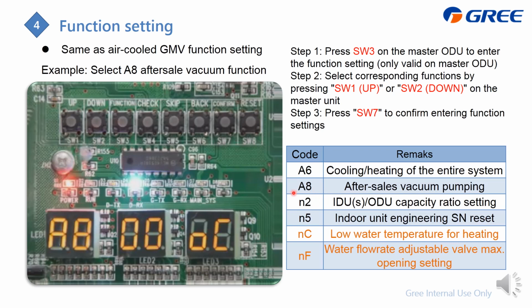Next is N2. N2 is to change the indoor unit divided by outdoor unit capacity ratio. The default setting is 135. The upper limit you can change it to is 150. And N5 is to reset all the indoor unit engineering SN. That means the address. And NC is to change the low temperature for heating, and later I will display this one. And also NF is to change the water flow rate adjustable valve max opening setting.